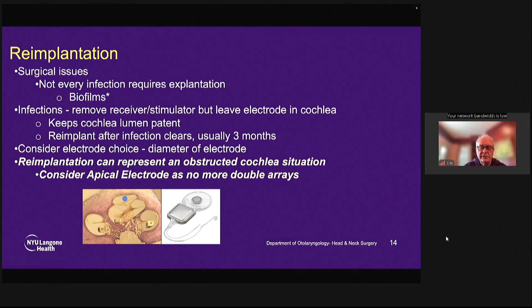Something we've been doing more recently, we're working on a project in regular cochlear implantations with apical low frequency hearing. So you would have your electrode in the basal area, and then you drop the ground electrode into the apex, and then you can stimulate between this electrode and the apex and get more sound. We have used this in obstructed cochleas lately because there are no more double arrays, or a double array has to be special ordered, which can take months to get. Isn't good.